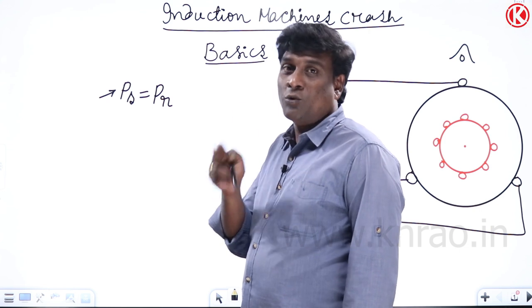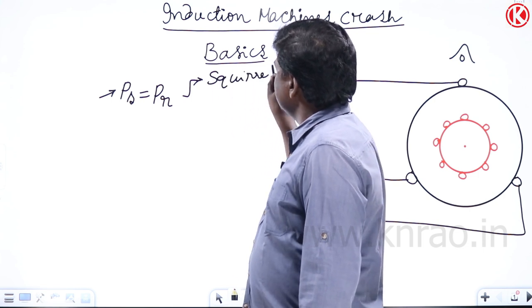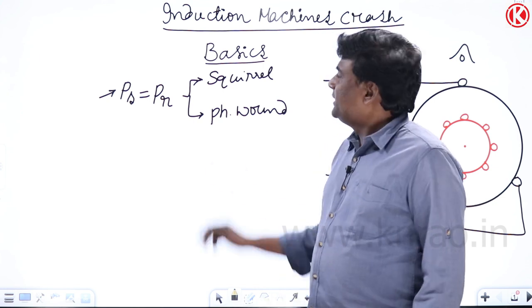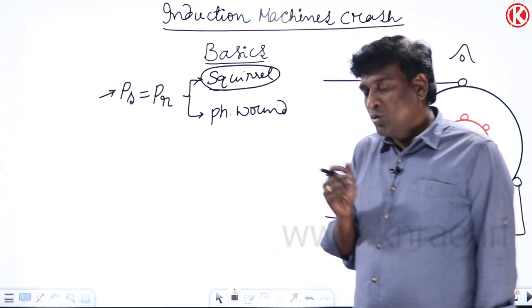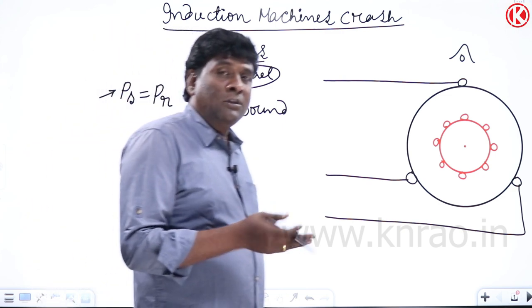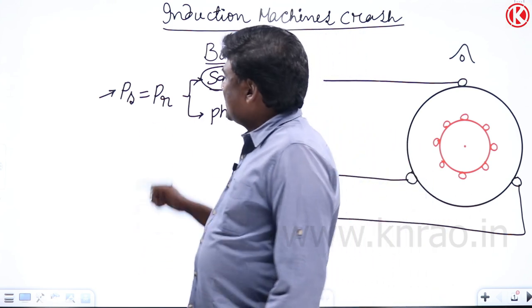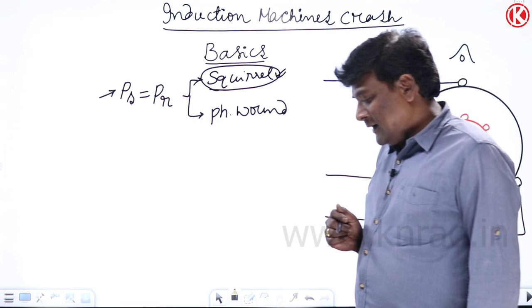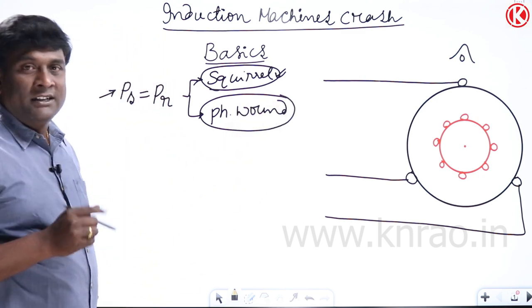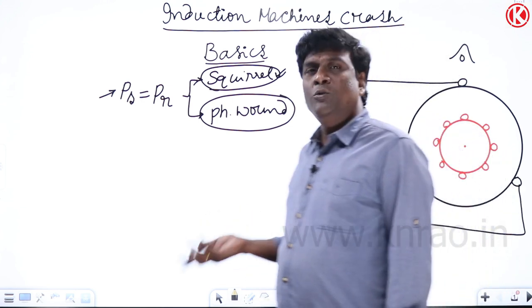In induction machines there are two types of rotors: squirrel cage rotor and phase wound rotor (slip ring rotor). A squirrel cage rotor can be used for any number of stator poles — two pole, four pole, or six pole — because it automatically produces the required poles. For phase wound rotor, you must intentionally design the rotor so that stator and rotor pole numbers are the same.